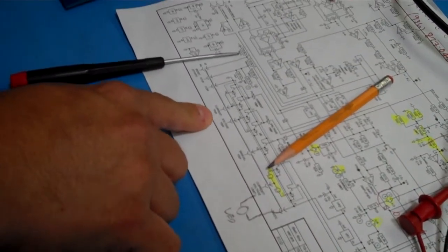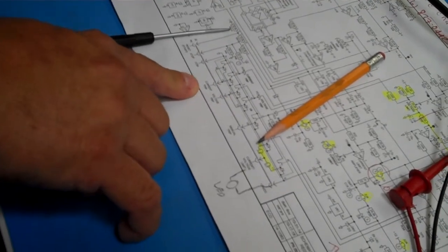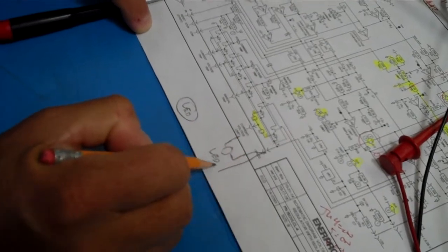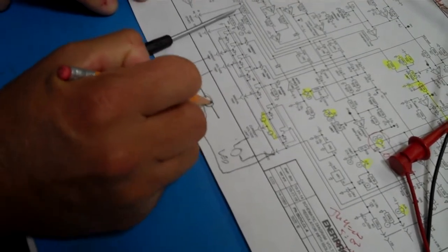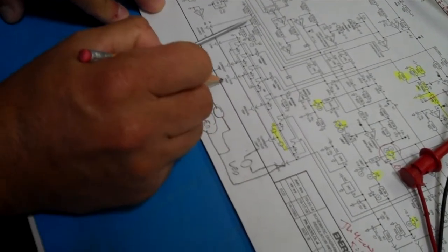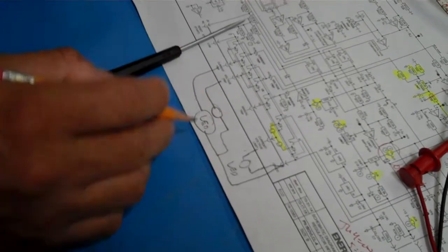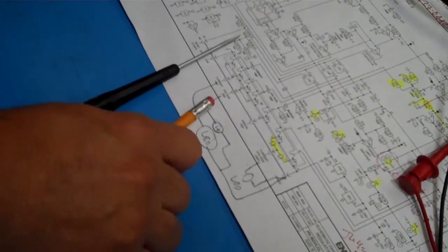Now the reason why I chose this is because you have JU6 and JU7. For the manual trip, the voltage trip, and the current trip, you don't have an option. So there are constant outputs. So if I were to have another LED or a relay between 24 and the current trip, every time I have a current trip, not current limit, this LED will come on. If I have another LED between 24 volts and the voltage trip, every time I have a voltage trip, this LED or relay will energize or turn on. This is the end of this video.